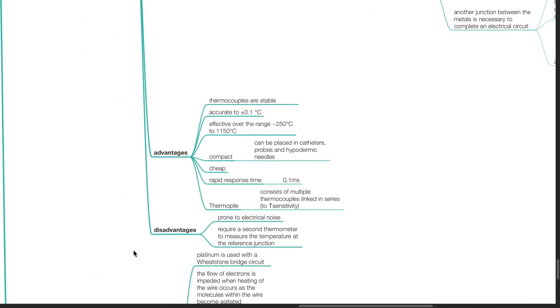Advantages of thermocouples: they are stable, accurate to plus or minus 0.1 degree Celsius, effective over the range of negative 250 to 1,150 degrees Celsius. They are compact and can be placed in catheters, probes and hypodermic needles. They are cheap, with a rapid response time of 0.1 milliseconds. They can be made into a thermopile — multiple thermocouples linked in series to increase sensitivity. Disadvantages: thermocouples are prone to electrical noise and may require a second thermometer to measure the temperature at the reference junction.